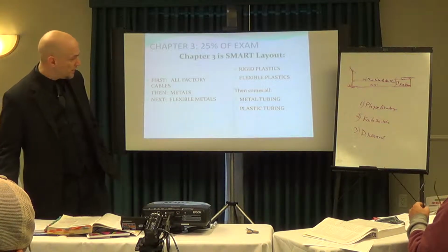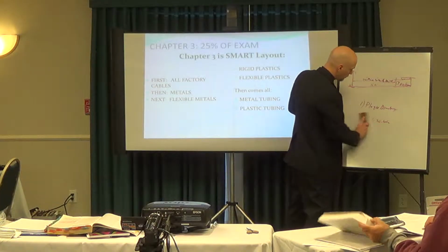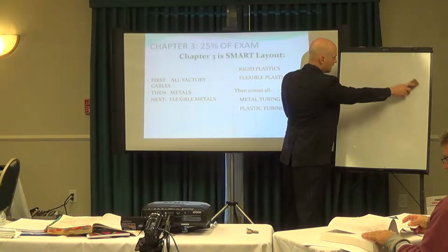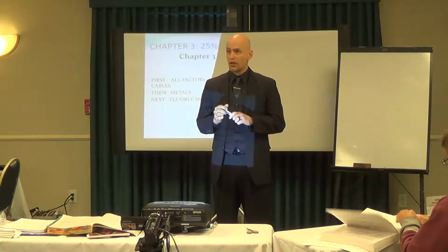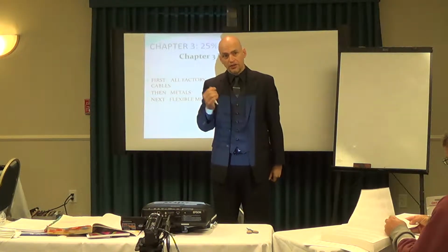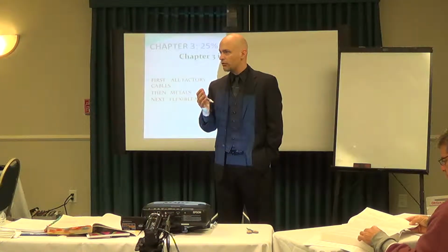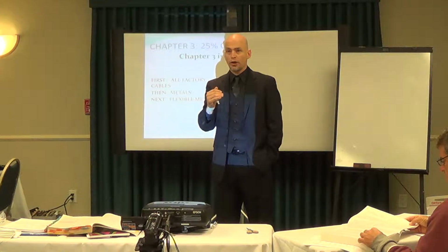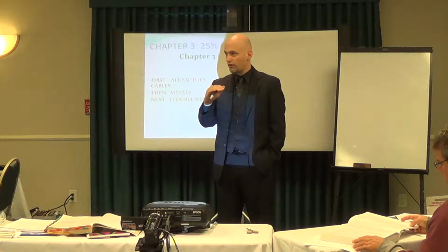Interrupting current is one of those things that, if you look at a breaker, standard molded-case circuit breaker, we're talking about a device that has two types of protection in it. We're real comfortable and understand the thermal part of it real well. That stamp that's on the little handle, it says 20 or 15 or whatever, it's 200 amps, whatever, that's a thermal rating of that breaker. Meaning that the overload protection of that device is whatever that rating is.